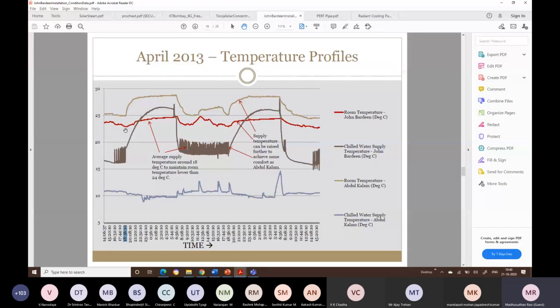Whereas the block which was using radiant cooling did not exceed the temperature 25 degrees centigrade even in the morning, and then once the chiller started, at the same time, they just switch it on. At no point, even in this 2-3 day data, you can see that the temperature has been below 25 regularly, whether the system is running or not. Okay. Why is this possible?